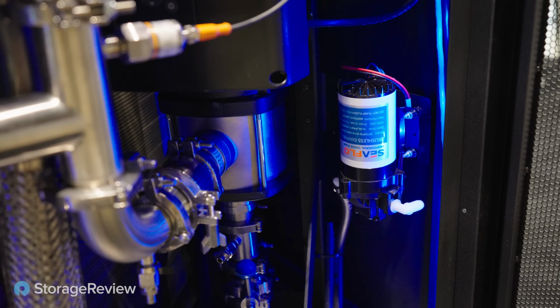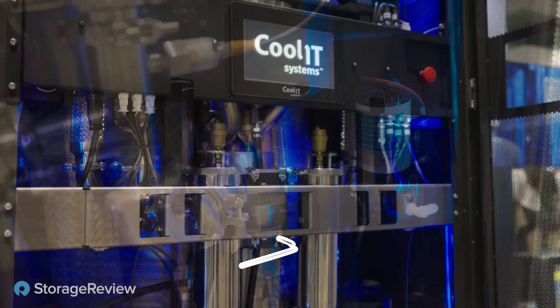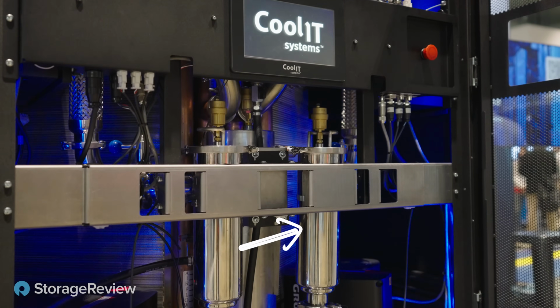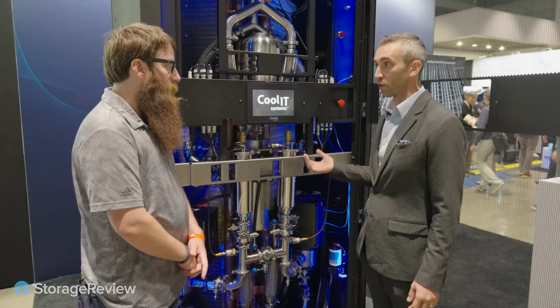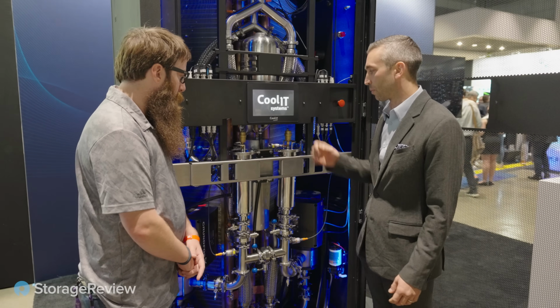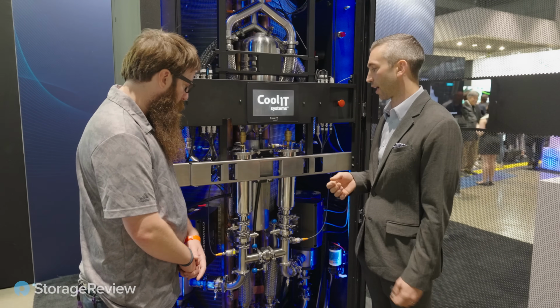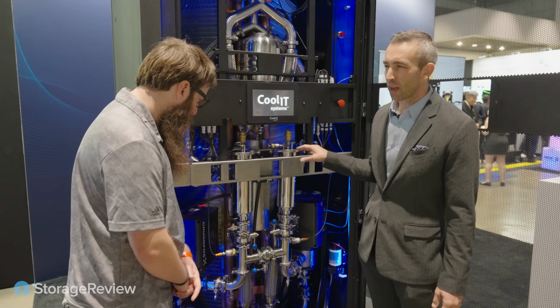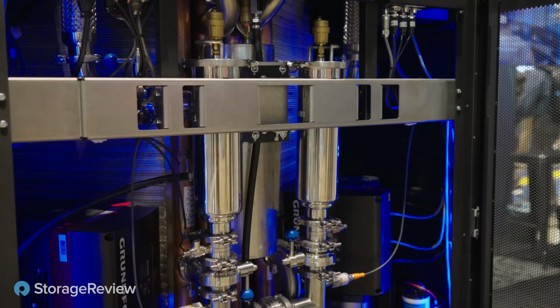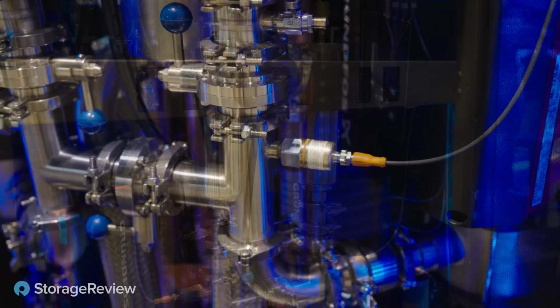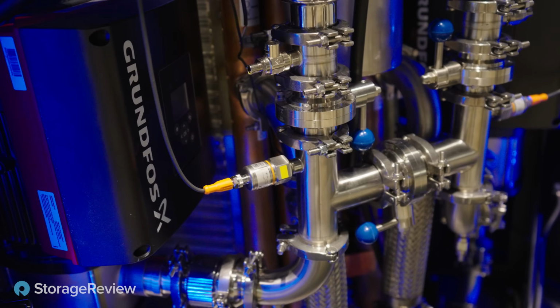Those pumps are pushing fluid through filters. These are redundant, both the pumps and the filters, and they're serviceable, so we change and clean filters and replace them as part of maintenance activities on the system. It comes in 25 micron and 50 micron variants. You see the reservoir in the back, with different fluid level sensors to know when the system needs to be topped up with fluid.